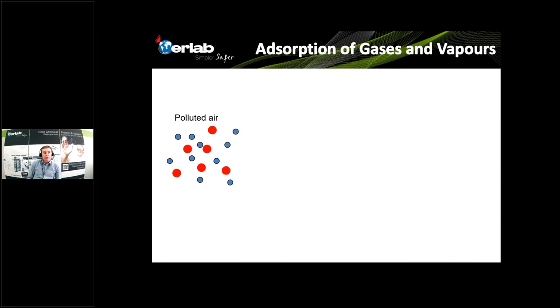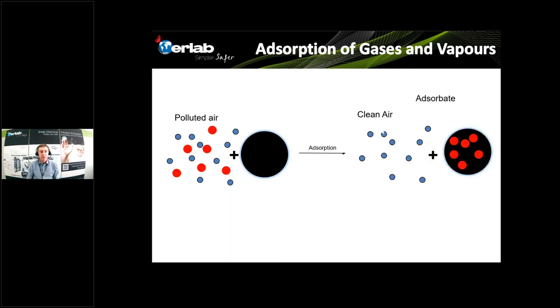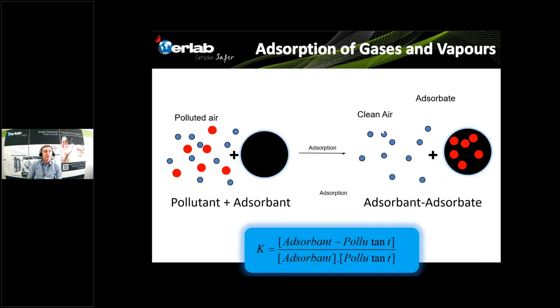When we talk about gases and vapors, we cannot use a network of fibers to trap them because the gas molecules are too small. In that case, we use a chemical reaction called adsorption. The idea is to create a reaction between a mix of polluted air and a material that will adsorb the pollution. At the end of the reaction, the pollution is absorbed onto the surface of the material — most of the time activated carbon. As with any chemical reaction, there is also a reverse reaction called desorption.